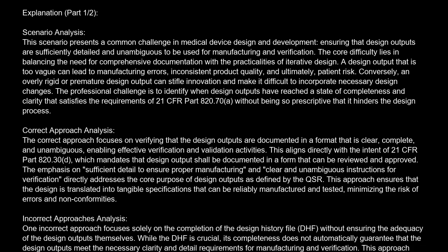Correct answer is C. The design outputs are documented with sufficient detail to ensure proper manufacturing and include clear and unambiguous instructions for verification. Explanation. Scenario analysis. This scenario presents a common challenge in medical device design and development, ensuring that design outputs are sufficiently detailed and unambiguous to be used for manufacturing and verification.